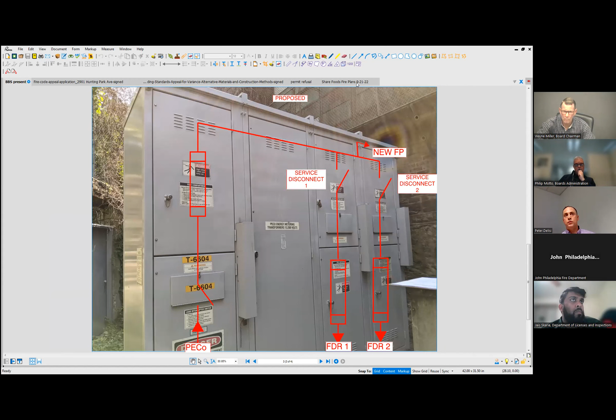Absolutely, when you're putting in a new pump, that's where you look at the old service, and I wouldn't put in something new with anything old. If we're saying we had a failure on the fire pump, that would lead me to believe I want everything new, including the service. I see 3 different fails before this, so to take this fire pump out means this whole entire building does not have a fire suppression system.